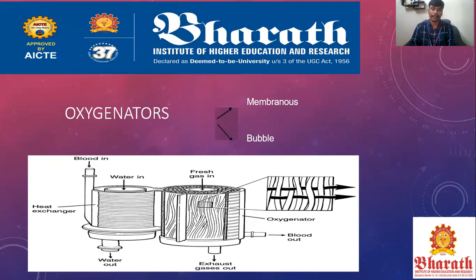Water inlet and outlet are there, and water is circulated through the heat exchanger continuously, which helps the blood stay in its state without clotting. After the heat exchanging process, the blood is given to the oxygenator, where fresh O2 gas is embedded into the blood, and the unwanted waste, the CO2 molecules, are removed and exhausted to the gas outlet.